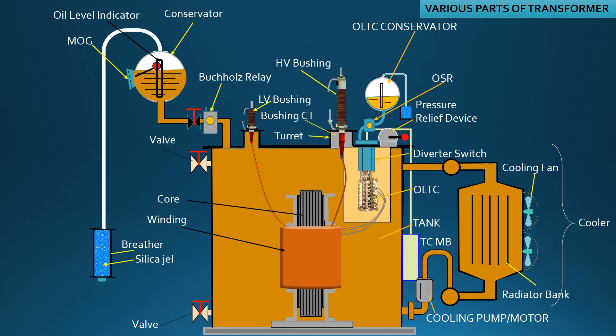Hot oil is drawn by cooling motors to the radiator fins where the hot oil radiates heat to the air outside by fanning action. Normally heat is radiated to the air surrounding by radiator only when the load is low. Fan and motor increase the rate of cooling.